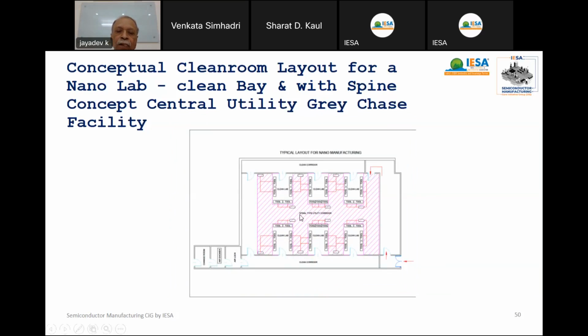One important thing here is these are all the white portions of the clean rooms. Maybe class 100, class 10, class 1000. So 6 modules you can see. One important thing is we have designed a separate type of utility corridor. Whatever utilities you need, you take all along this. So you can see we are shrinking the clean room to the minimum possible area. The utility corridor runs in the center. So whatever you want, electrical, compressed dry air, DI water, can all be done in the center and connect to both the clean rooms.